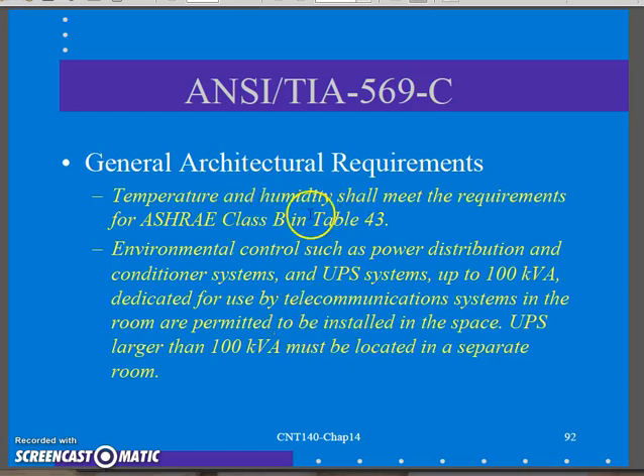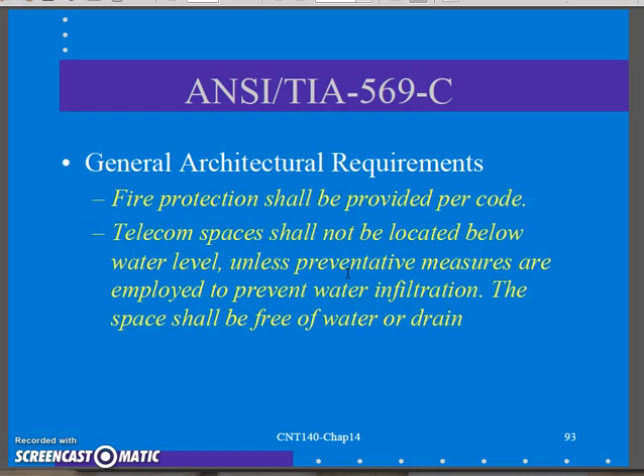Temperature and humidity were already mentioned — yes, you should have climate control in there pretty much year-round. They talk about environmental controls such as UPS, and they give a limit on how much UPS equipment should be in the closet. If you go over certain values, it should be located in another room, probably where your generator and other things are. Fire protection: any local fire codes should be followed in your closet as far as what's located in there, and that does change by county.